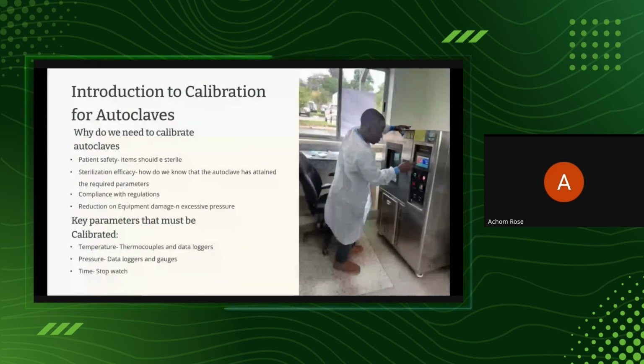This could be of different types. The common types are type K and type J, and we've seen also their stability. Type J and type K are a bit stable, but of course, in my working, type K is the most stable. So looking at that, but also you look at the size. Yeah, you find that maybe the type J is slightly bigger, and once you put it in the autoclave and try to close, you're going to have leakages.